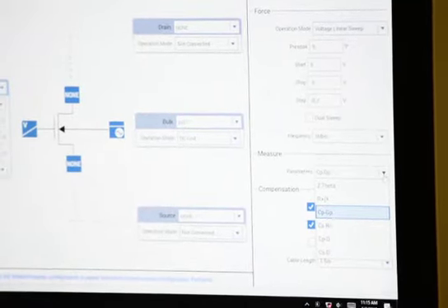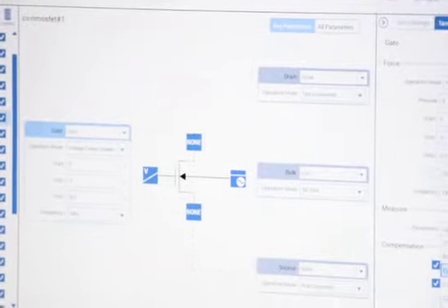Make sense? Yeah. So it's a separate test, but you can get a lot of information off of this AC bridge. It's like a 4-step process. It could be, yeah. If you're confident with your dissipation factor, then you don't have to do it, but I recommend you do it, just so you know you got good results.